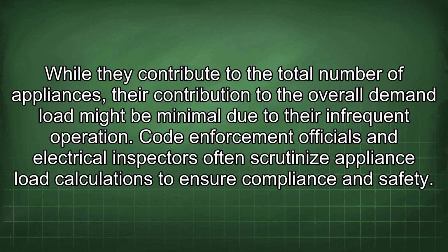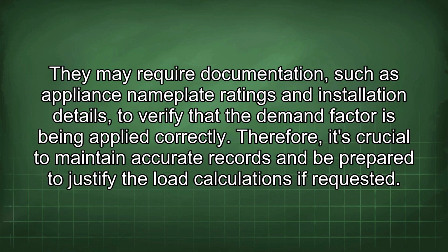Code enforcement officials and electrical inspectors often scrutinize appliance load calculations to ensure compliance and safety. They may require documentation such as appliance nameplate ratings and installation details to verify that the demand factor is being applied correctly. Therefore, it's crucial to maintain accurate records and be prepared to justify the load calculations if requested.